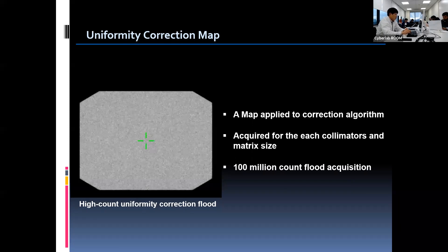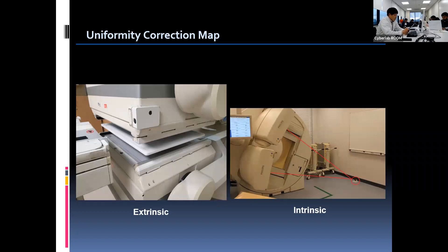The correction map must be acquired for each collimator and matrix size used for clinical SPECT imaging. The acquired count is about 100 million, which is approximately 10 times more than that of daily uniformity tests. Uniformity calibration can be done either extrinsically or intrinsically. However, it takes more time to complete as it requires much higher counts. The cobalt sheet source can also be used for extrinsic uniformity correction, providing uniform distribution of photons.